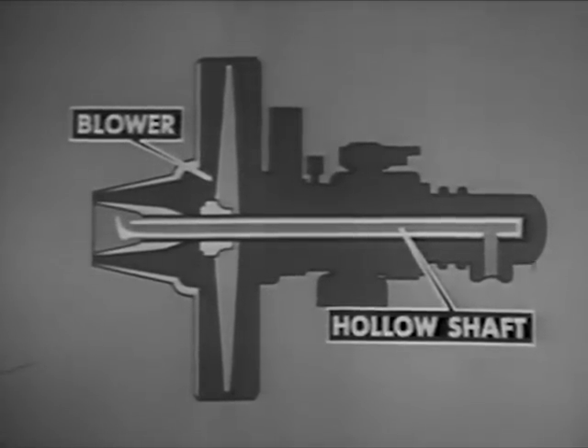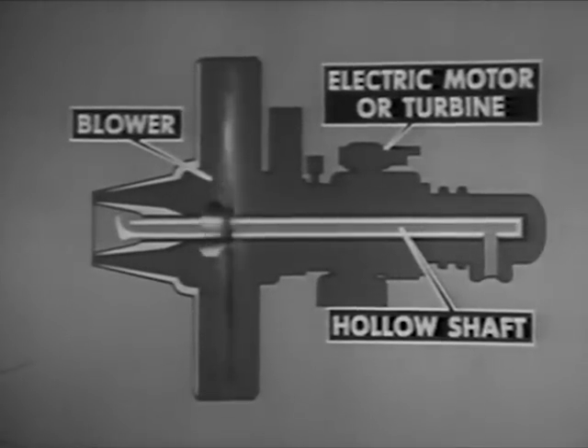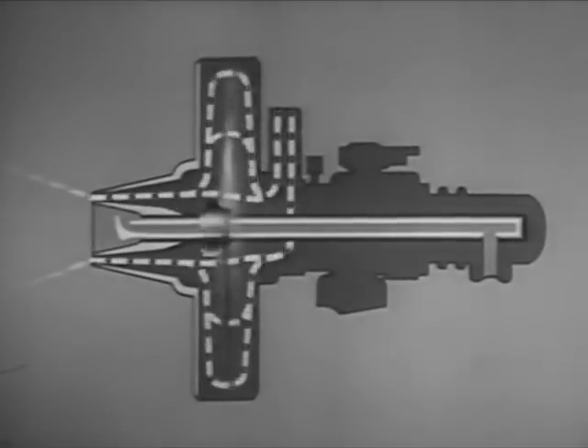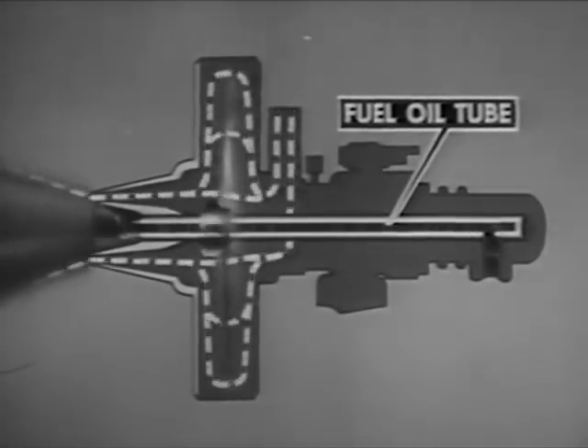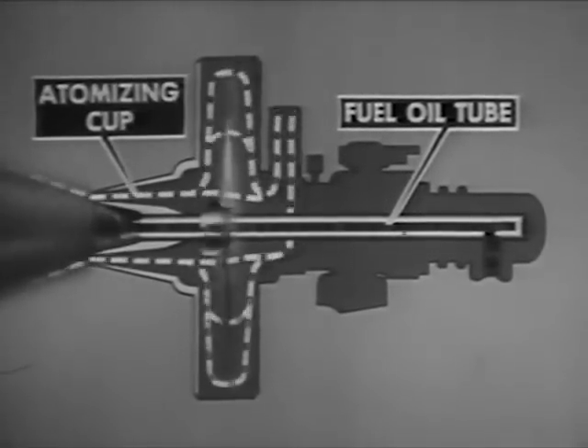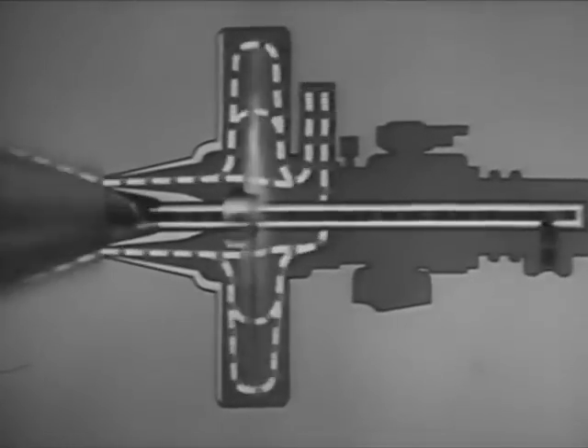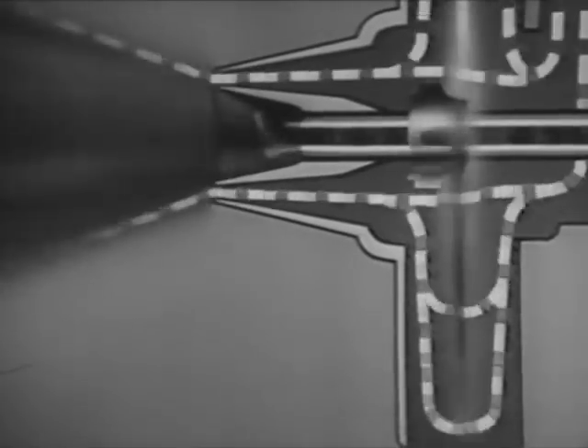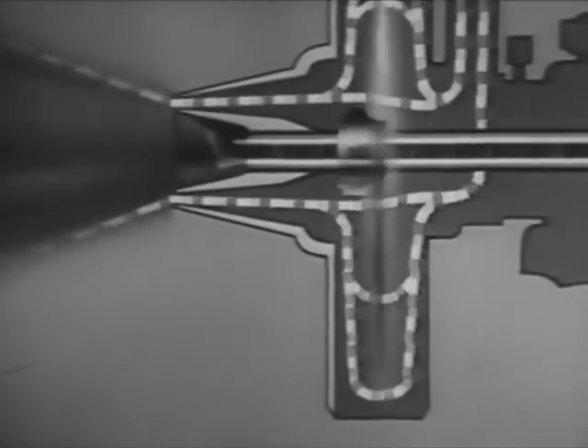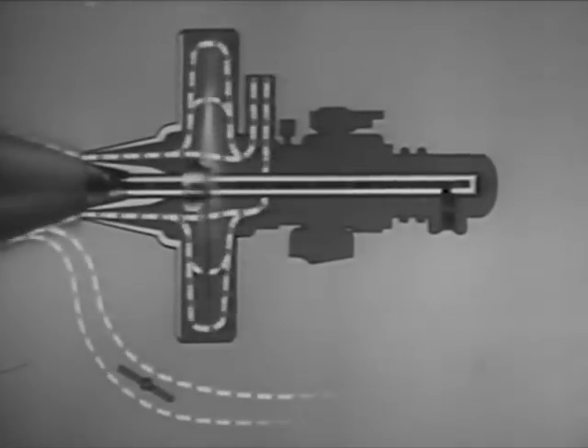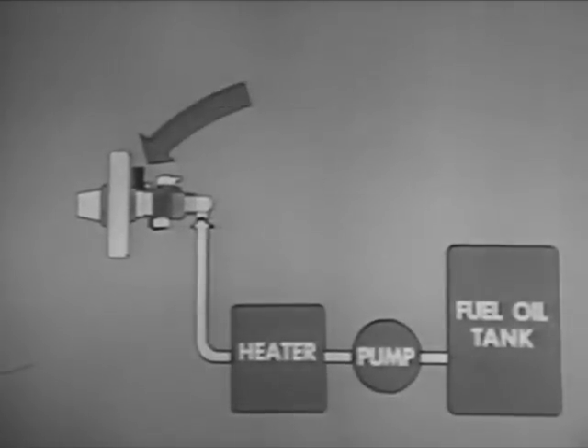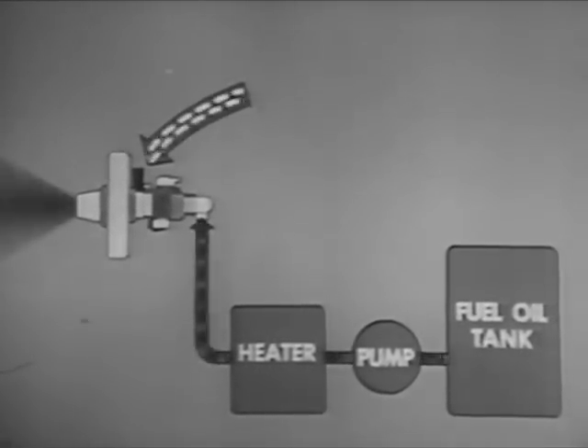In the rotary cup burner, a fan or blower is mounted on a hollow steel shaft. An electric motor or steam turbine turns the shaft and blower at high speed, providing a blast of air around the burner nozzle. The oil, under low pressure, enters through a stationary fuel oil tube inside the rotating hollow shaft and is discharged into the rotating atomizing cup. Centrifugal action forces the oil against the inner surface of the atomizing cup and causes the oil to leave the rim as a hollow cone. The meeting of the oil and the air from the blower further atomizes the oil. Additional air needed for proper combustion enters through an air door in the furnace wall. As in all burners, you control the firing rate by controlling the amount of fuel oil and air going to the burner.